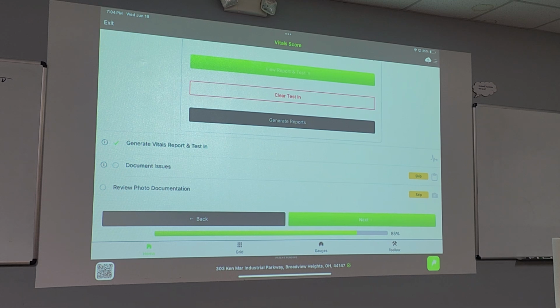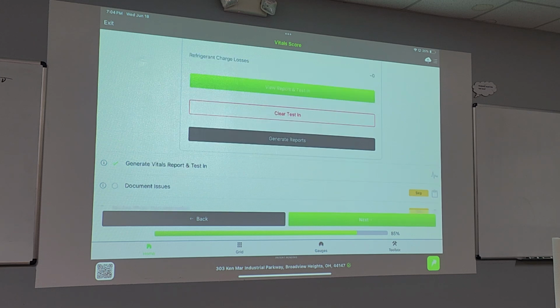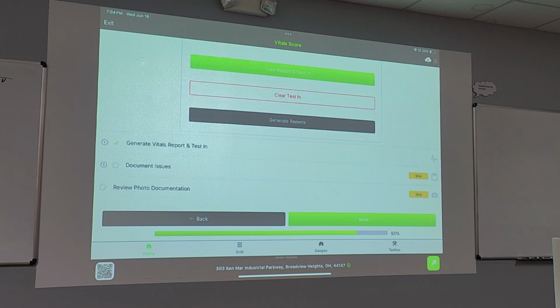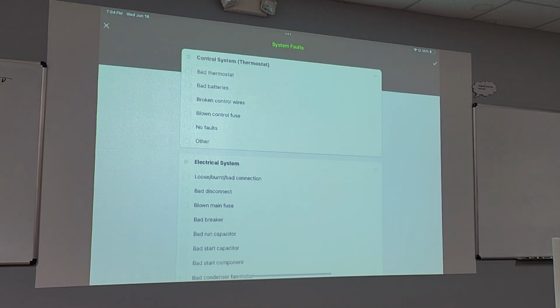So back to the gauges, at this point you're still customer facing. You showed the customer that vitals report. We've got a slightly undercharged condition. You can gas this thing up a little bit, get your subcooling closer to 10. Probably not much is gonna do to help that superheat get into range given the heat load, but you're still facing the customer right now. So you can show them that, you can show them any issues you've identified so far.